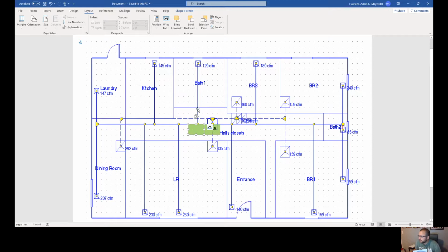All right, so right now I'm not worried about sizing those runs, but I need to know how much came out of it. I didn't really need to know that it was a 6-inch right now. I'm just showing you how that works. I'm just worried about the trunk right now. So this first piece of trunk has to be big enough to carry everything on this end. We only have 800 available. Like I said, obviously my load is a little off. But we're going to have one in each room and probably a couple here in the living room. So I'm going to change these for simplicity's sake.